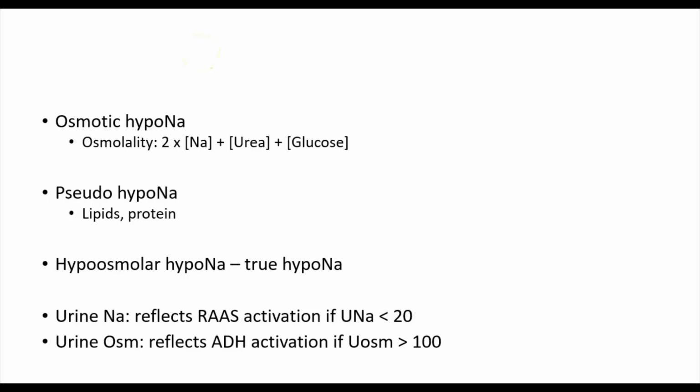The next entity is that of pseudohyponatremia, which is an artificially low sodium level due to the measurement method. Many chemistry analyzers use an indirect ion-specific electrode method to determine the concentration of electrolytes like sodium. This involves a pre-dilution step prior to actual measurement with the electrode, and then this measured level is converted to a final reported level based on the degree of dilution.